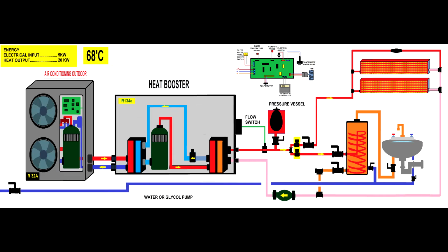So this system, as you'll see, you have the outdoor, then you have a plate heat exchanger that is a refrigerant to refrigerant temperature exchange, and then I have on the other side R134a, another plate heat exchanger which exchanges the heat with the water. And then I have a pump which circulates the water through the system, and this is my heat pump system.